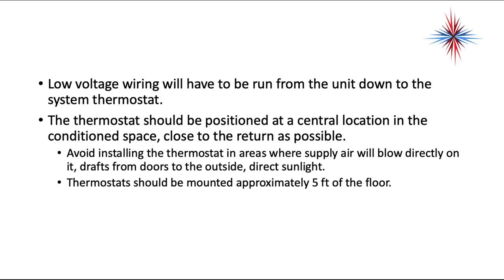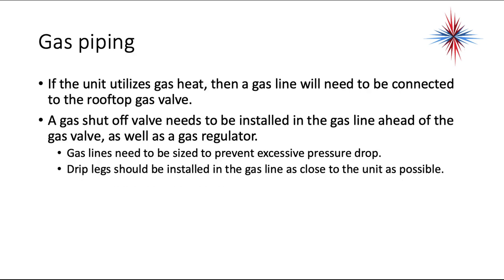Low voltage wiring will have to be run from the unit down to the system thermostat. The thermostat should be positioned at a central location in the conditioned space, as close to the return as possible. Avoid installing thermostats in an area where supply air will blow directly on it. You also want to avoid drafts from doors to the outside and direct sunlight. Thermostats need to be mounted approximately 5 feet off the floor.